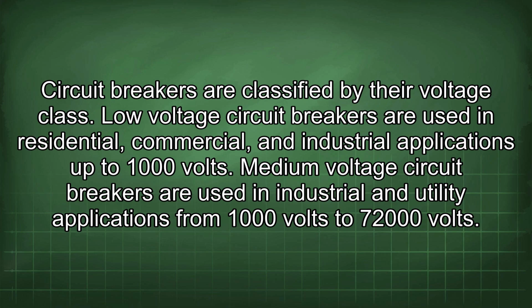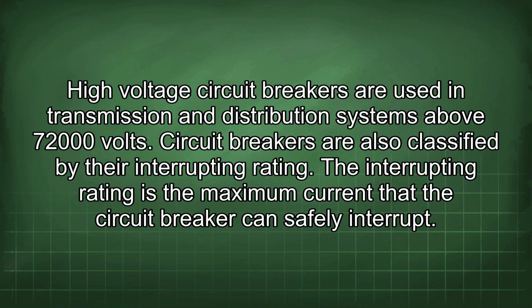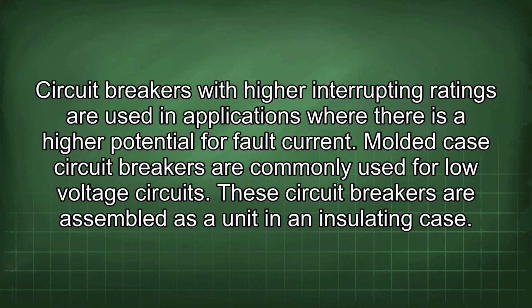Low voltage circuit breakers are used in residential, commercial, and industrial applications up to 1000 volts. Medium voltage circuit breakers are used in industrial and utility applications from 1000 volts to 72,000 volts. High voltage circuit breakers are used in transmission and distribution systems above 72,000 volts. Circuit breakers are also classified by their interrupting rating. The interrupting rating is the maximum current that the circuit breaker can safely interrupt. Circuit breakers with higher interrupting ratings are used in applications where there is a higher potential for fault current.